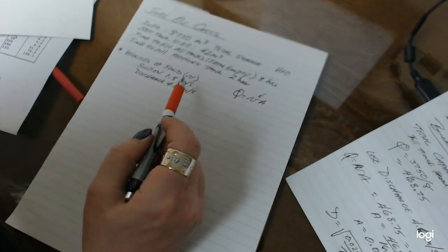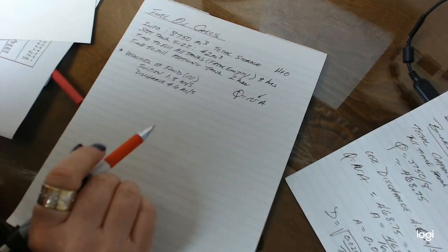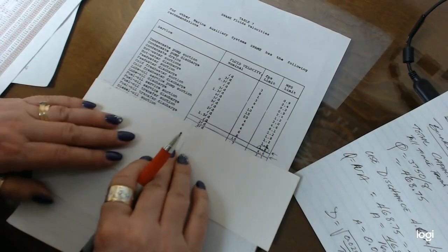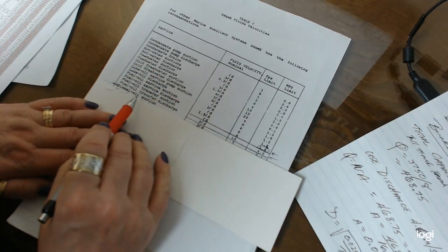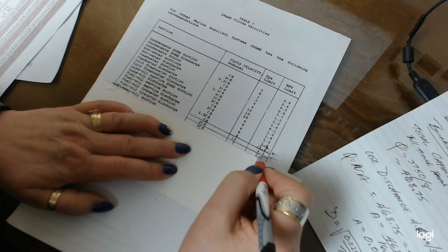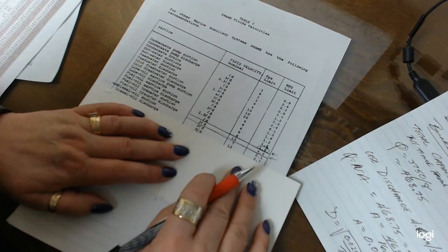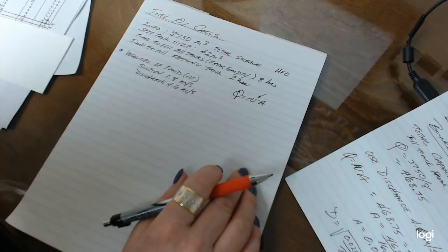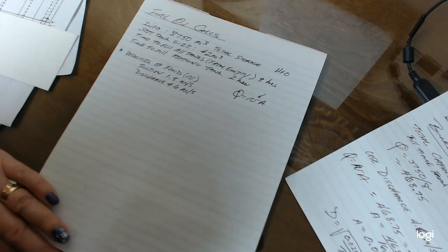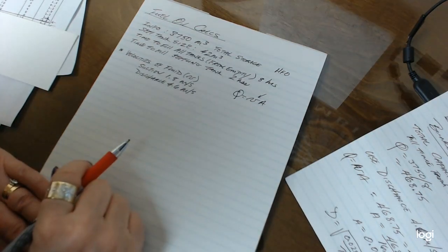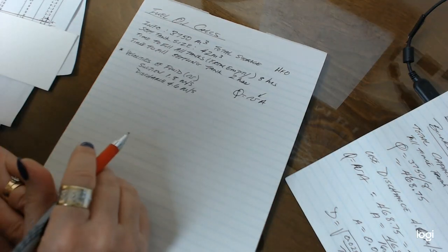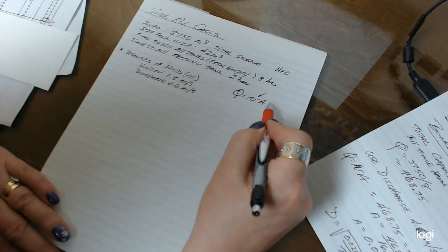So you'll note that I've put these numbers here. I also want you to pay attention that these numbers are in meters per second. If you're using diesel fuel as your setup, notice that there's a separate line over here for diesel. So diesel would use for the suction 2.1 meters per second, and for the discharge it would use 3.7. Now, of course, if we're going to use our same pipes for both suction and discharge, we will have to calculate both and use the largest. So how I'm going to set this up initially is I'm going to show you how to calculate using your fuel setup, finding the area that we need to move this through, and eventually give you a pipe size.